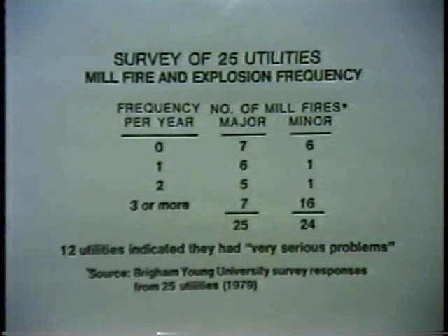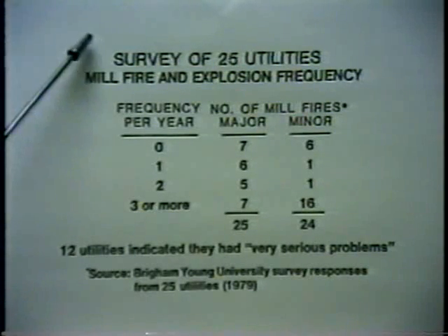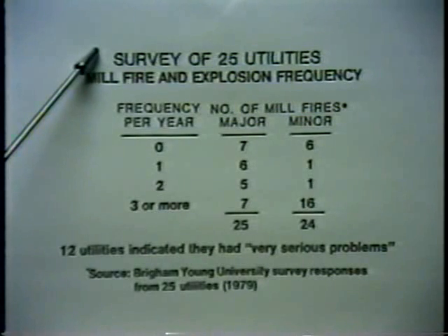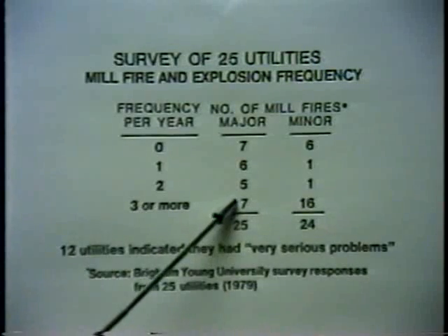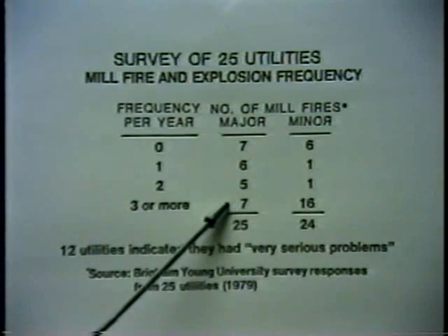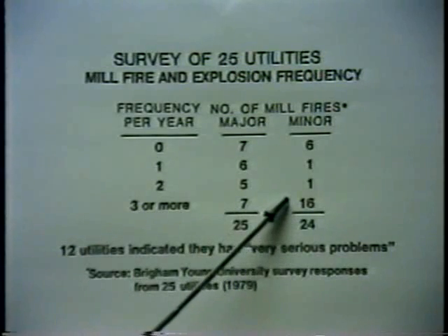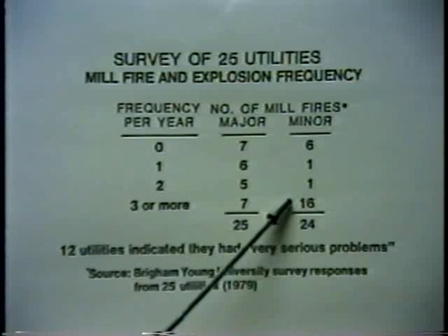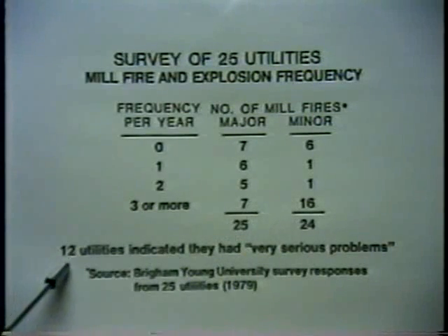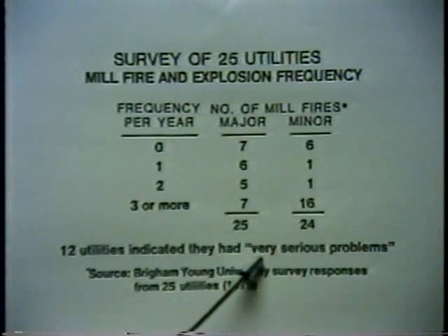The report revealed that explosions consistently occur given an ignition source when the fuel-air mixture is leaner than the normal mill operating condition. The survey noted the frequency at which coal fires occur. Drawn from a sample of 25 utilities, it was found that 7 utilities reported 3 or more major fires per year. 16 utilities had 3 or more minor fires per year. 12 utilities indicated that they had very serious problems.